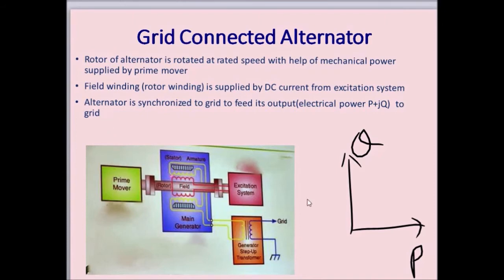In order to feed this active power and reactive power into the grid, the alternator has to be synchronized with the grid. This means the alternator stator winding voltage must be the same as the grid voltage, the phase sequence of the generated voltage must be the same as that of the grid, and the electrical frequency of the grid must be the same as the electrical frequency of the generated voltage.